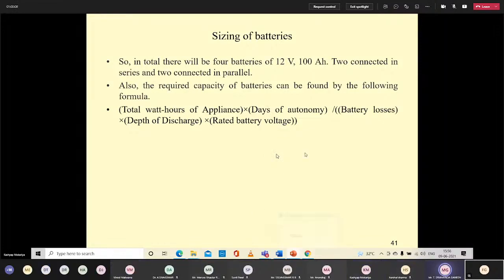Power generation. So without any power generation, without getting grid support, how your battery will supply the load, that is basically the day of autonomy. Now, here it is very tricky. If you select a day of autonomy as 5 days, then obviously the sizing of the battery will increase and the cost of your system will increase. If you have a nominal day of autonomy of 2 or 3, then you have a limited backup for a limited time. So obviously that is also designed for a particular system, depending on what you want to do, what budget is there with you and what typical backup you want to provide.